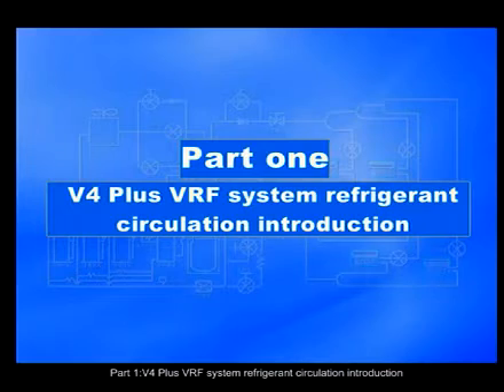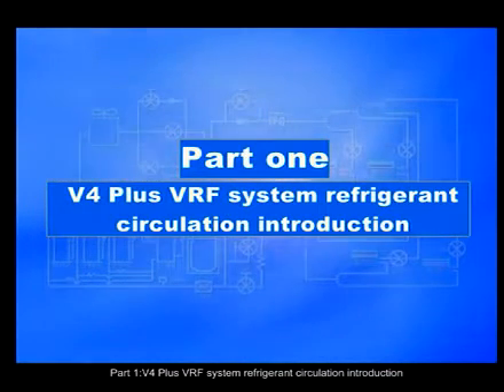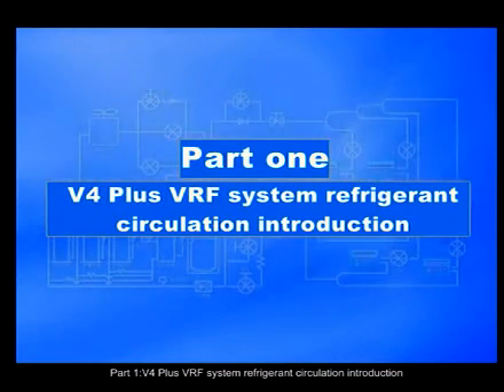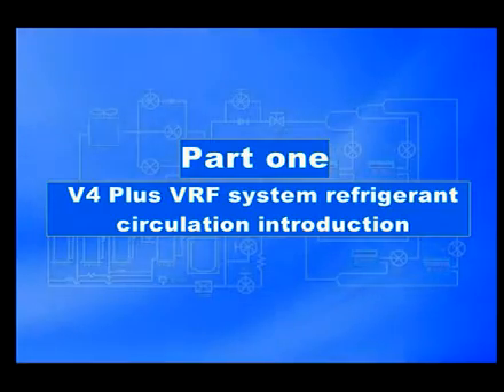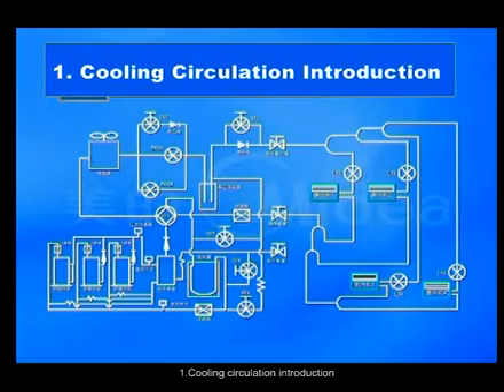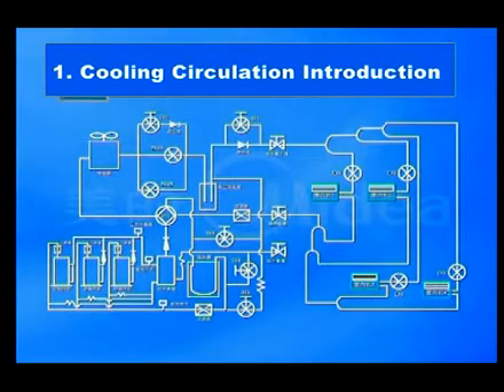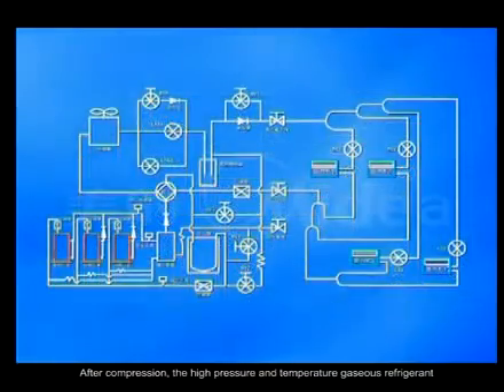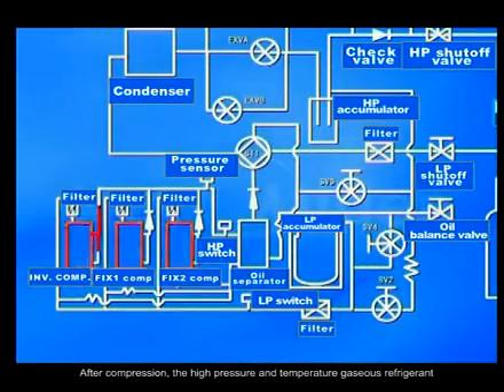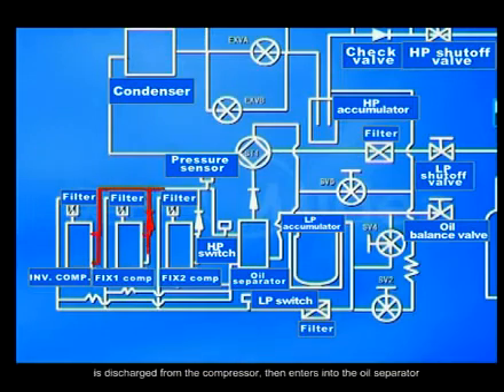Part 1. V4 Plus VRF System Refrigerant Circulation Introduction. 1. Cooling Circulation Introduction. After compression, the high pressure and temperature gaseous refrigerant is discharged from the compressor, then enters into the oil separator.